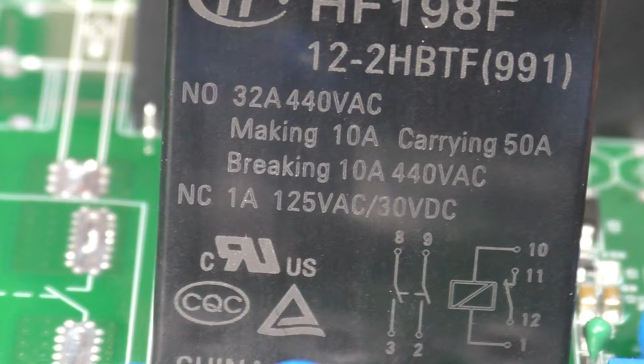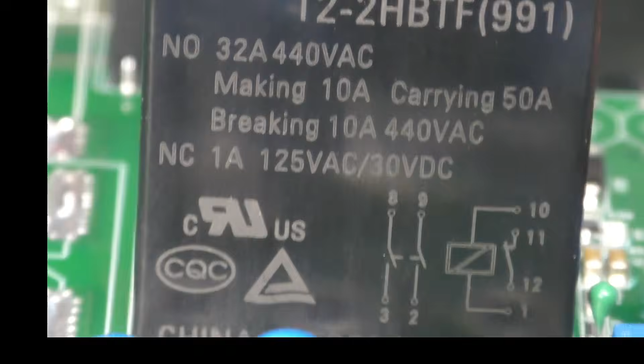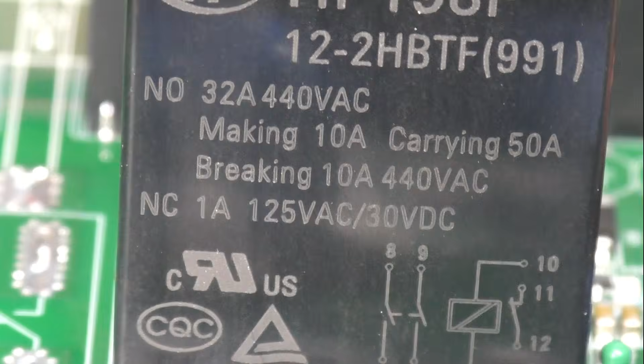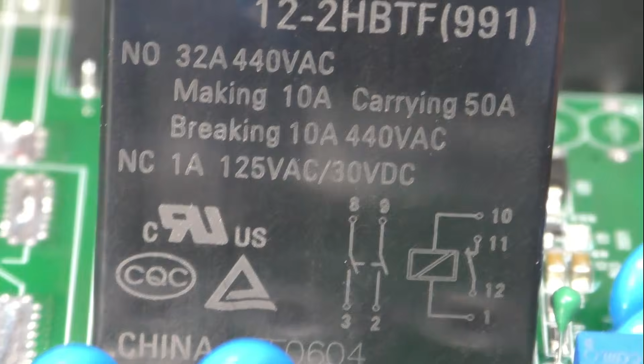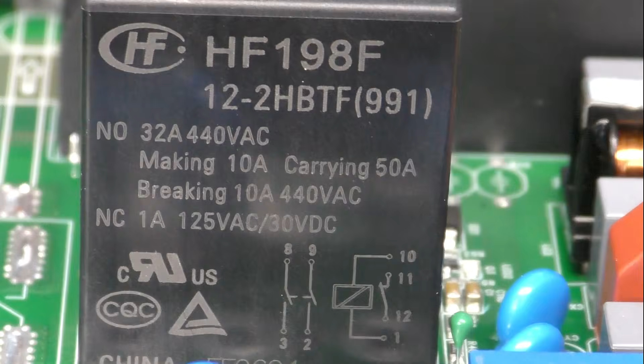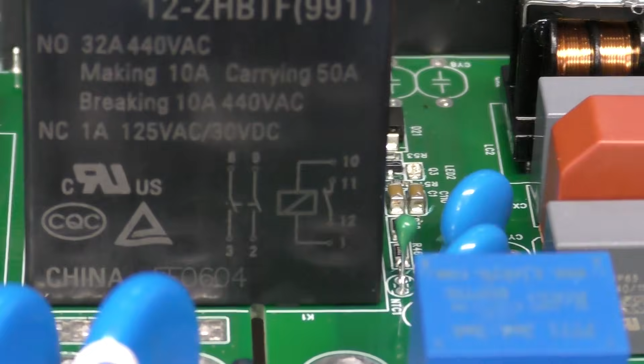In this application, this would never normally open or close under load because the car determines when to turn on - once it turns on, the car ramps up its current. So this should never see significant current during switching, meaning it's fine to have a relay only rated for 10 amps making and breaking, but capable of carrying the continuous load. I guess this is probably specially made for this application, so they don't carry the additional cost of a relay capable of making and breaking high current, but it can carry the current for extended periods without getting hot - exactly what you want here.